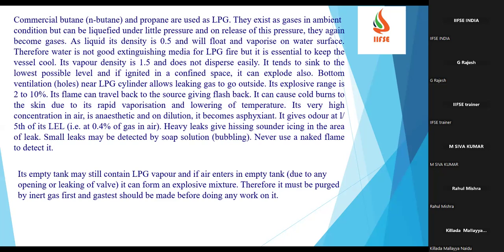It can cause cold burns to the skin due to rapid vaporization and lowering of the temperature. It gives odour at one fifth of its LEL, 0.4 gas in the air, and heavy leaks give a hissing sound and cylinder icing near the area. Hissing sound in the sense that in case of gas leakage, it generally gives a hissing sound, and there the ice gets formed. Even with a CO2 fire extinguisher, once you start operating, the hose will get very cold. Near the nozzle, you can see the ice formation.